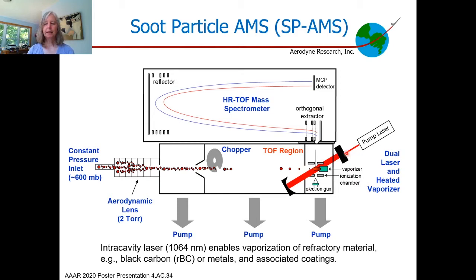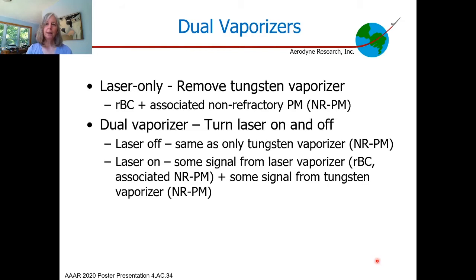The SP-AMS incorporates a 1064 nanometer laser into the vaporization and ionization region of an aerosol mass spectrometer. This allows us to detect material that absorbs at 1064 nanometers, such as black carbon and metals, and their associated coatings.